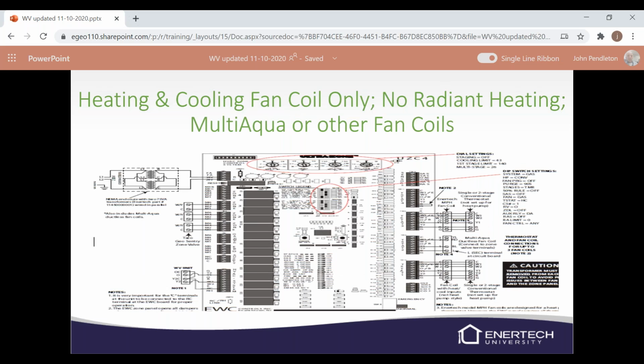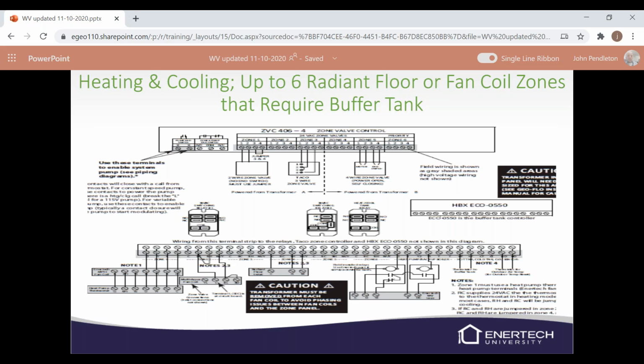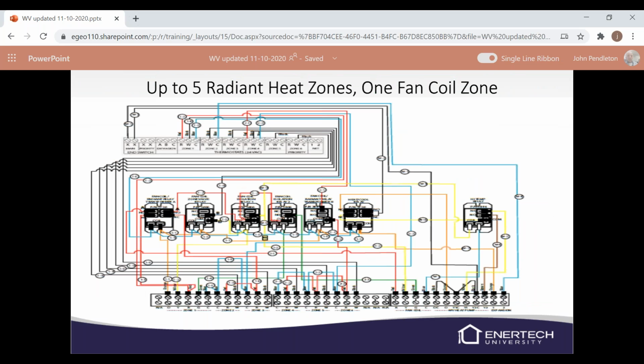And here's another one. We've got heating and cooling, fan coil only, and we're using a multi-aqua or another fan coil. There's some setups and things you have to do, but we've listed it pretty well in the IOM for you. This will be a heating and cooling up to 6 radiant floor or fan coil zones that we're going to require a buffer tank. So if you've got a buffer tank, this is going to be the setup for that. And we're going to use the HBX control on this setup, the HBX Eco 550. Just another little wiring diagram of the 5 radiant zones, 1 fan coil zone.